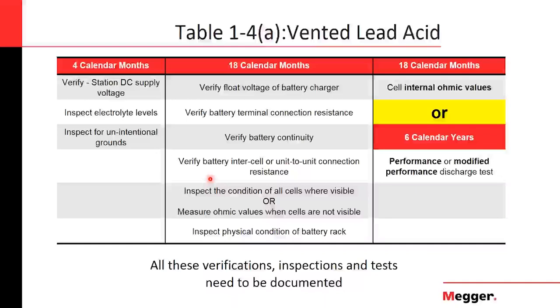Batteries have certain specs, they have certain capacity, and that's what everything is based on. All the backup that the battery can provide is based on that capacity. So NERC wants you to verify that the battery is going to meet that requirement. And there are two ways to do it according to NERC. You can do an inspection of the ohmic values every 18 months. Or, if you don't want to do that and you want to do a different test, you can perform what is called a performance test or modified performance test, which is also known as a discharge test or a capacity test.